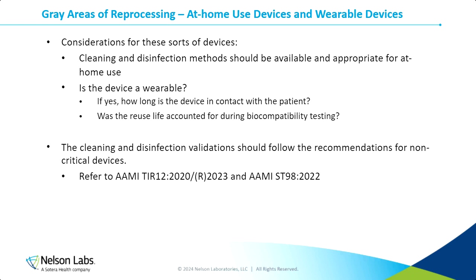You're going to want to also figure out how to determine the frequency of decontaminating the device. How often should the patient decontaminate the device if they're wearing it most of the time? Those are things you're going to have to consider. Typically, we see instructions to decontaminate the device as contamination is seen or visible, recommending that the end user clean the device. Another thing is, how are these validations going to be performed? As Brianna mentioned, ISO 17664-2 seems to allow for combination validations, to combine the cleaning and disinfection validation into a single validation study.